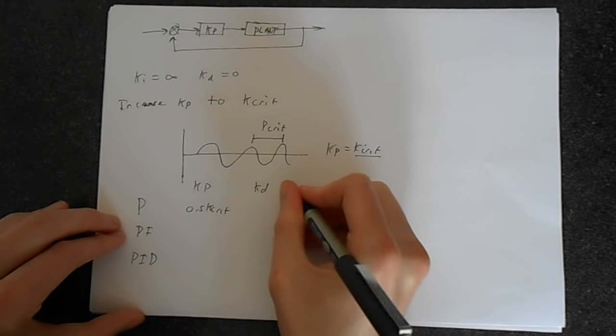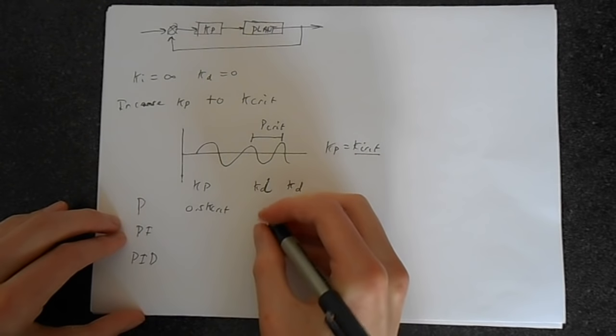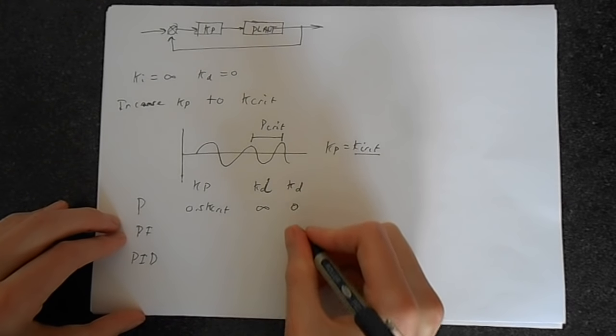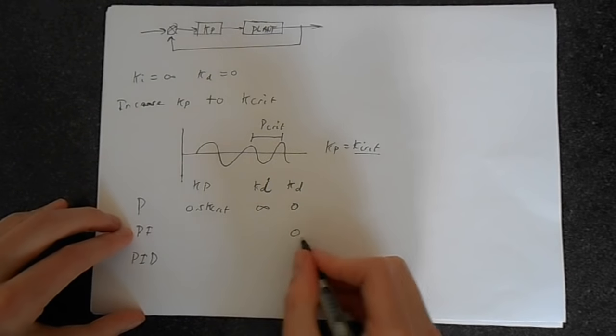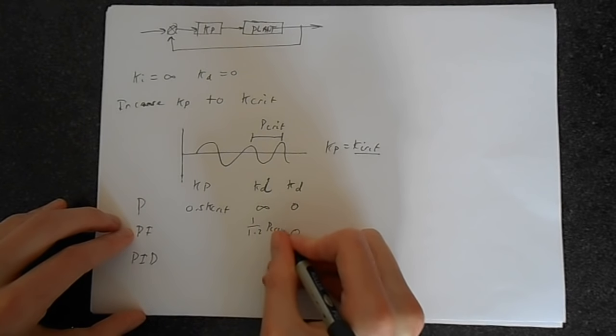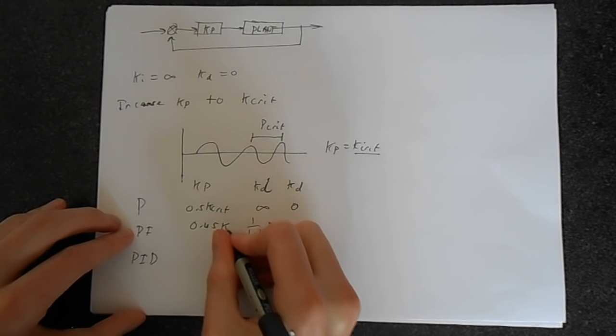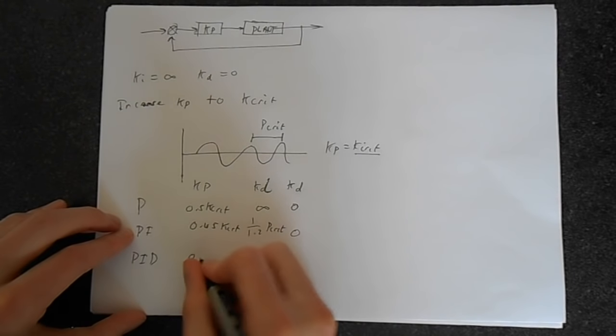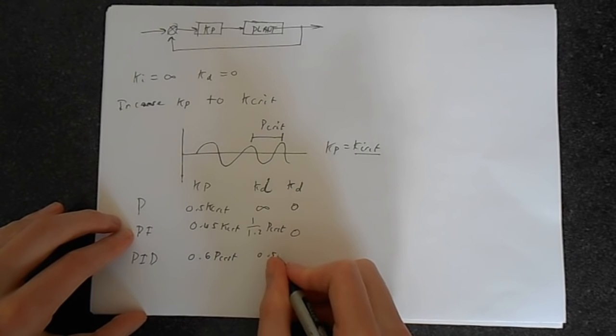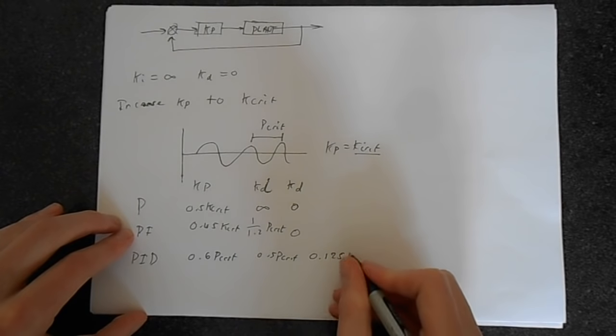So KP is 0.5 times kcrit. In this case, we've got KI here. So infinity, and then 0. Of course, no D. 0 here, no D. 1 over 1.2 pcrit. Here you've got 0.45 kcrit. 0.6 kcrit. 0.5 pcrit. And then 0.125 pcrit.